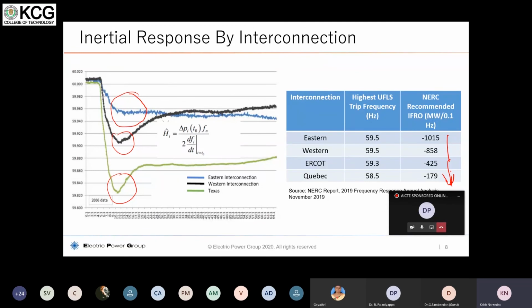Okay. Likewise, if you take ERCOT, only 425 megawatts, for every 0.1 hertz drop, you should make sure that the grid is stable within these operations. If it goes below this, that means there is a danger for ERCOT stability. So therefore, these things are very important. As I said, if you have more inertia in the system, obviously you can support such loss of megawatts, through the rotational kinetic energy that gets the power back to the grid.